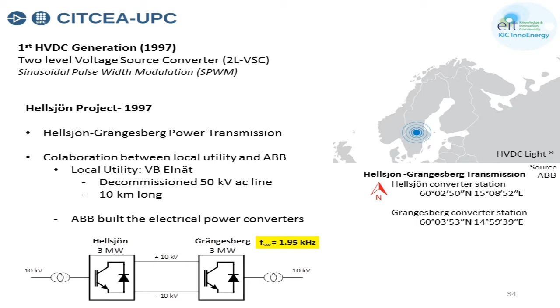This project is basically a demonstration project from '97. It was a collaboration between ABB and the local utility. The local utility had a 50 kV decommissioned AC line, and ABB used this decommissioned line to transmit power on DC using 2 VSC converters, plus minus 10 kV on the DC side, a 3 megawatt converter, also connected to an AC grid of 10 kV.